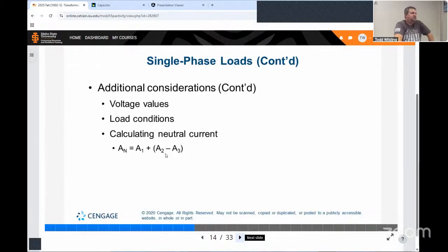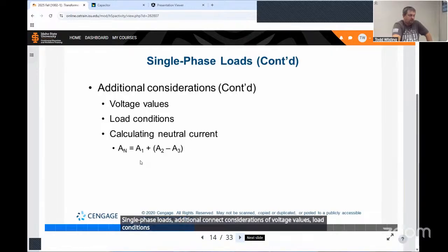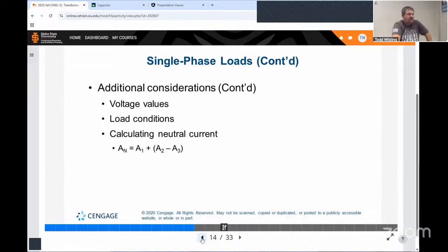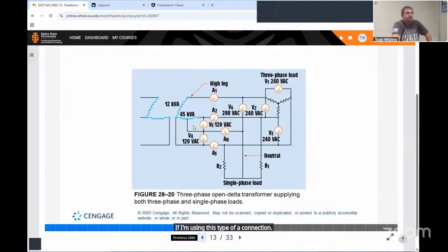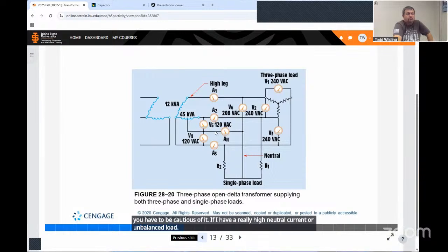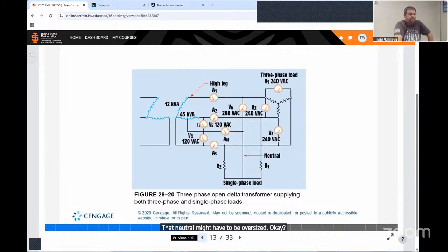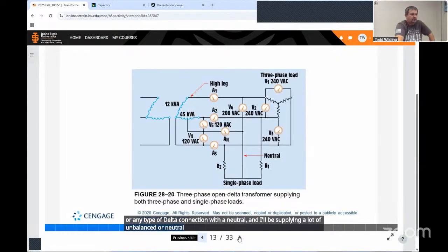Single phase loads, additional connection considerations of voltage values, load conditions, and calculating the neutral current. If I'm using this type of connection, my neutral current, you have to be cautious of it. If I have a really high neutral current or unbalanced load, that neutral might have to be oversized. So pay special attention if I've got an open delta or any type of delta connection with a neutral and I'm supplying a lot of unbalanced or neutral loads on there.